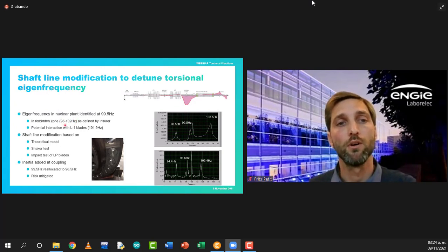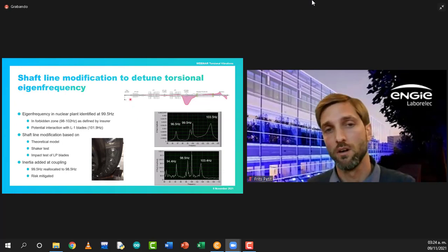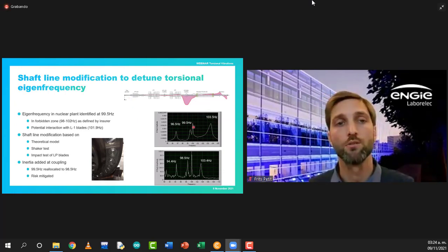For instance, here for the insurer of the nuclear plant we're considering here, it was between 98 and 102. But measurements revealed that we had a natural frequency very close to 100 Hertz, 99.5 Hertz. So this was not acceptable by the insurer. And we had to do a shaft line modification. So a theoretical model of the shaft line was set up. We did a shaker test on site to confirm the natural frequency. We did an impact test of the LP blades because these had a frequency close to the natural frequency, close to 100 Hertz, and could interact as well in the deformation.